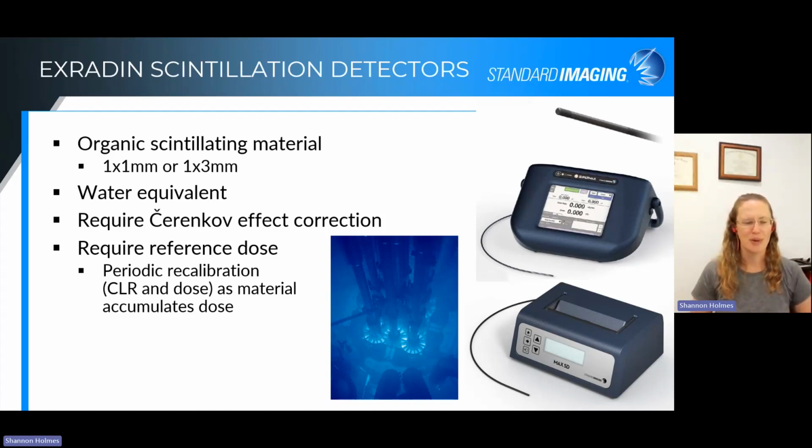So I think most of us have seen old PMMA phantoms, old clear plastic phantoms that have been irradiated a lot. They start to turn yellow after a while with all of that radiation dose, and the same phenomenon affects our optical measurements with the scintillation detector. So that decreases the signal that can pass through the yellowed fiber and also changes the spectrum slightly, which changes how we would correct for the Cherenkov.